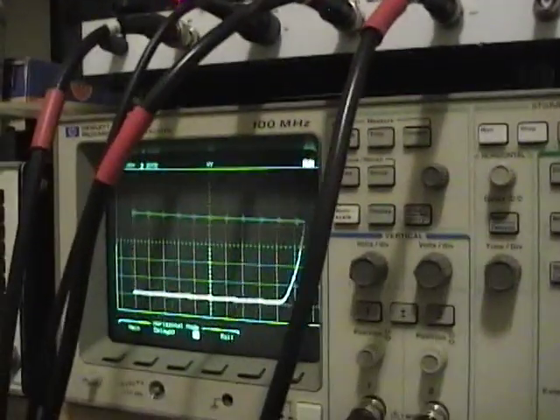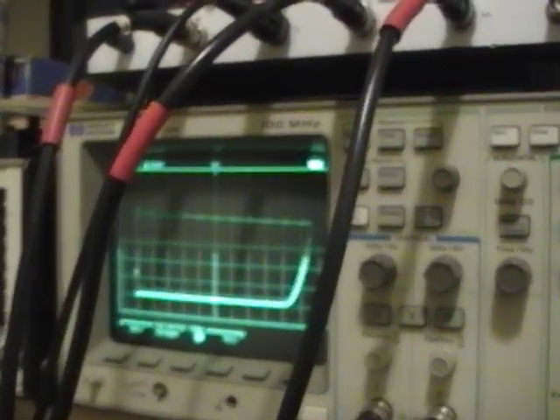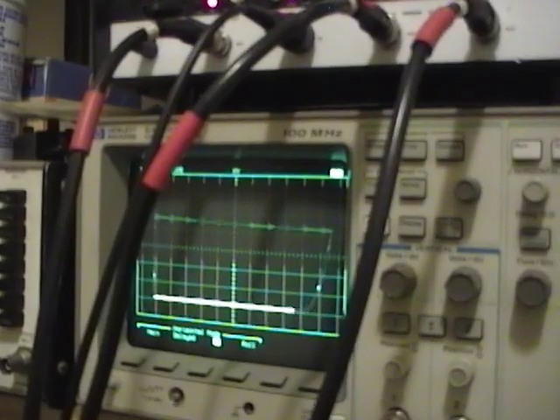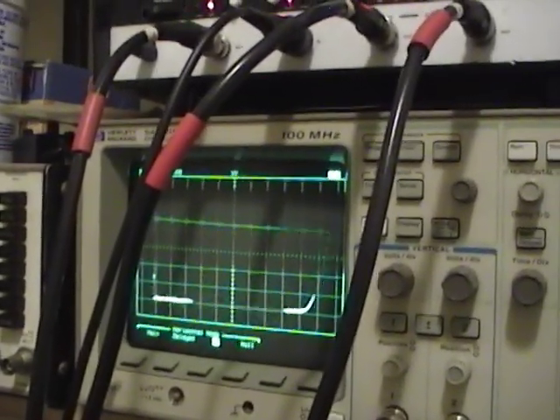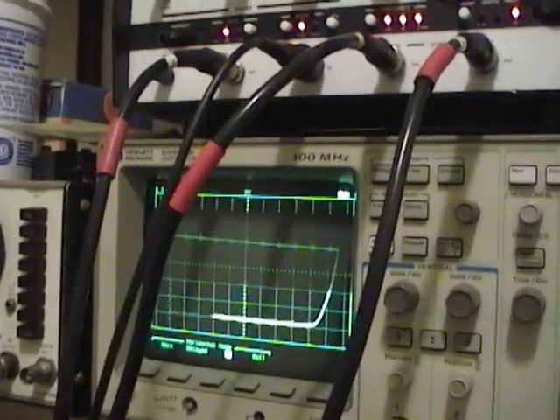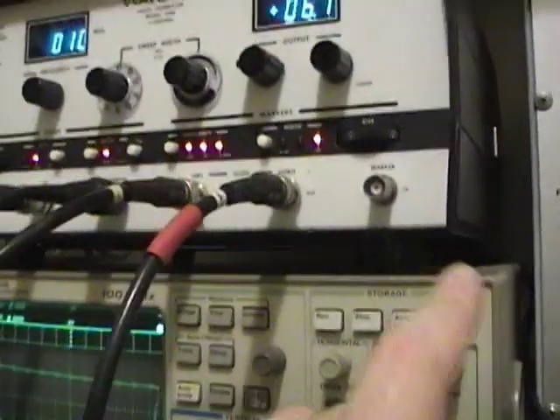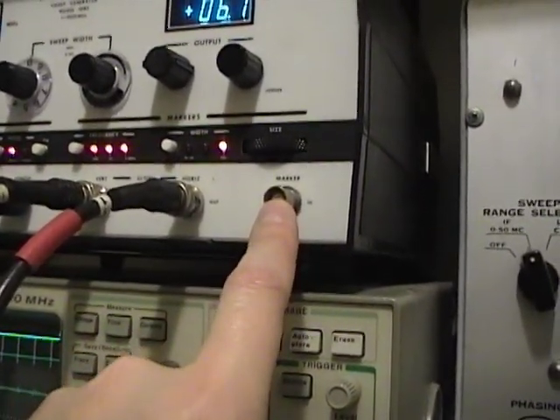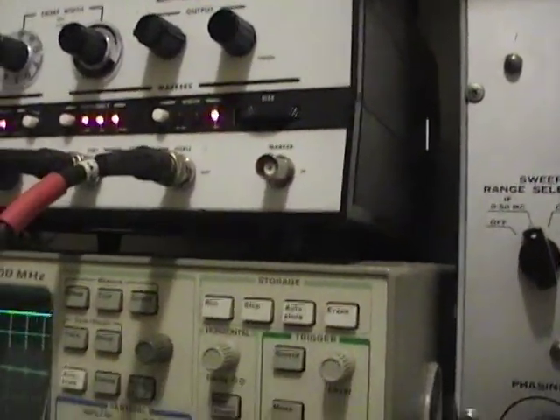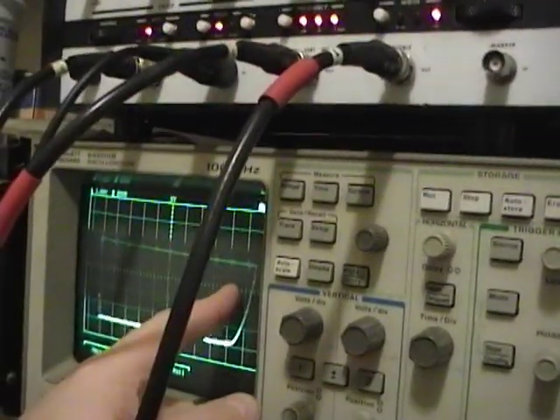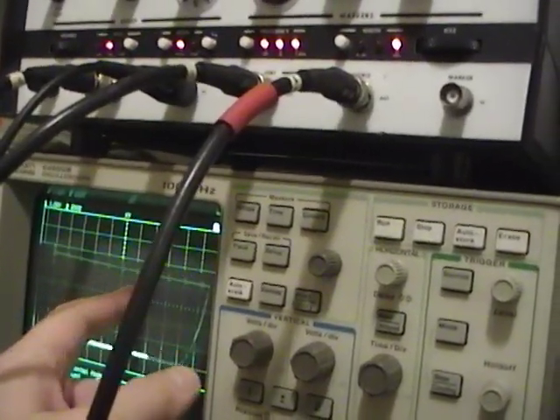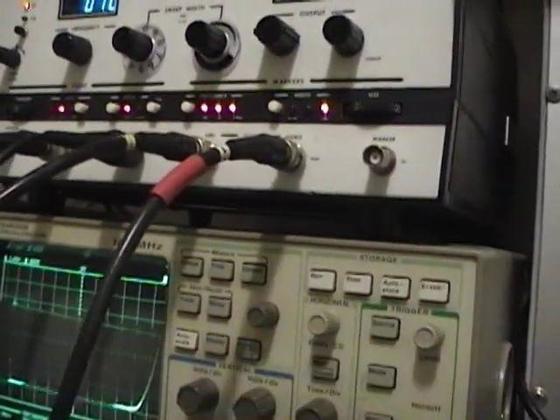So that's the basics of how a sweep generator works. So now what I want to do next is... oh by the way, I should mention you can also input a variable marker in here. So if you took an RF generator and hooked it into here, you can still have all these stationary ticks at the one megahertz and ten megahertz increments, then you have a variable one.